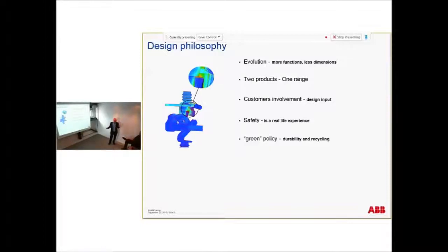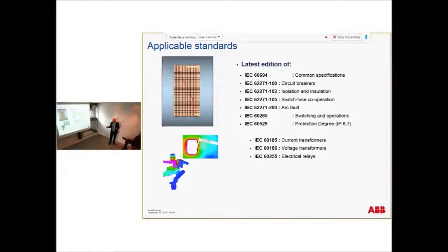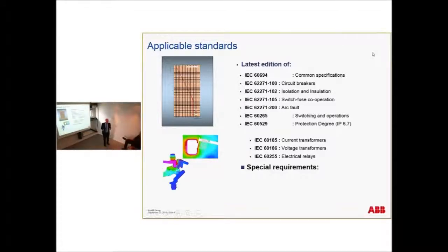Firstly is the development, which is a key issue, and the IEC norm. Our switchgear, I think we had a small talk in this break, is designed according to IEC classification. So for America, ANSI, this is not ANSI qualified. This IEC classification is valid for Europe, but also in Asia with some special GB standard for the Chinese, GOST for Russia, EDF for the French market, and DIN VDE for the German markets.